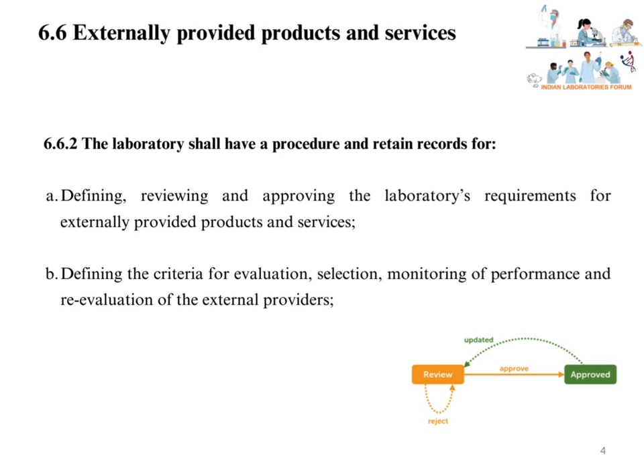The laboratory shall have a procedure and retain records for defining, reviewing, and approving the laboratory's requirements for externally provided products and services, and for defining the criteria for evaluation, selection, monitoring of performance, and re-evaluation of external providers. This clause demands a procedure for selection, evaluation, monitoring performance, and re-evaluation of vendors, as well as an approval process for vendors, with clear procedures for different types of vendors or service providers.